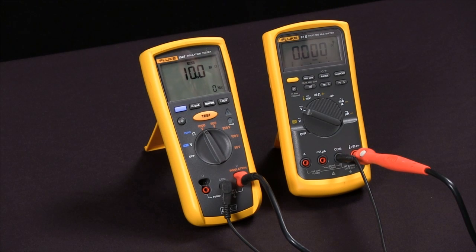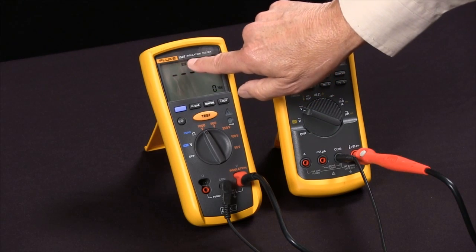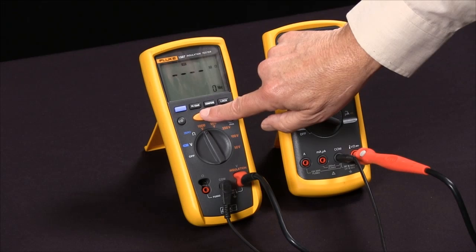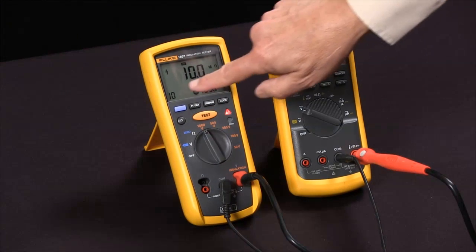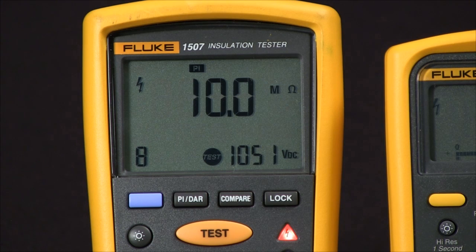Polarization index is done the same way. I select polarization index PI and 1,000 volts, and I push the test button. It begins a 10 minute test, so you see 10 minutes, and that will count down. At the end result, it will show the ratio.